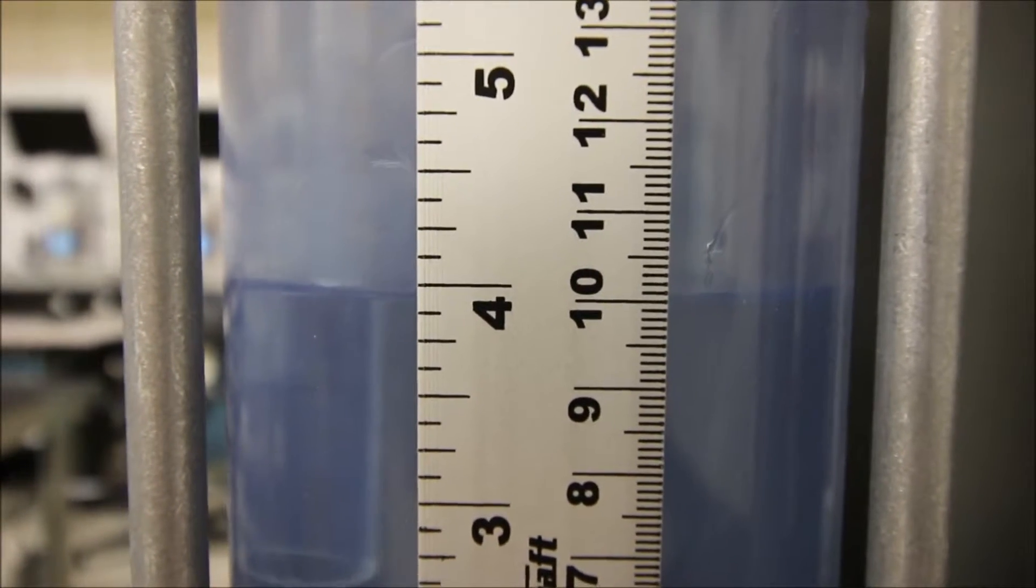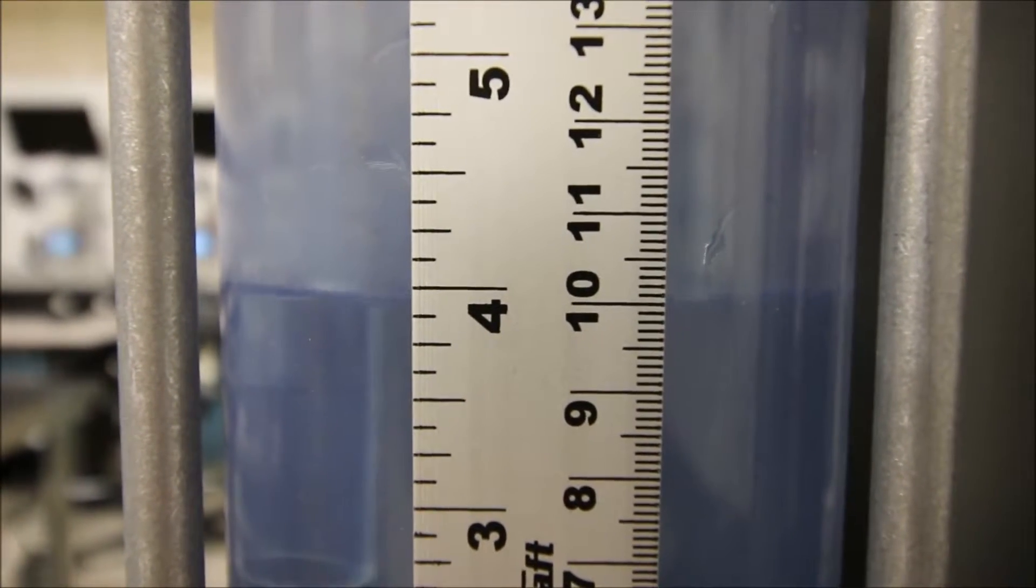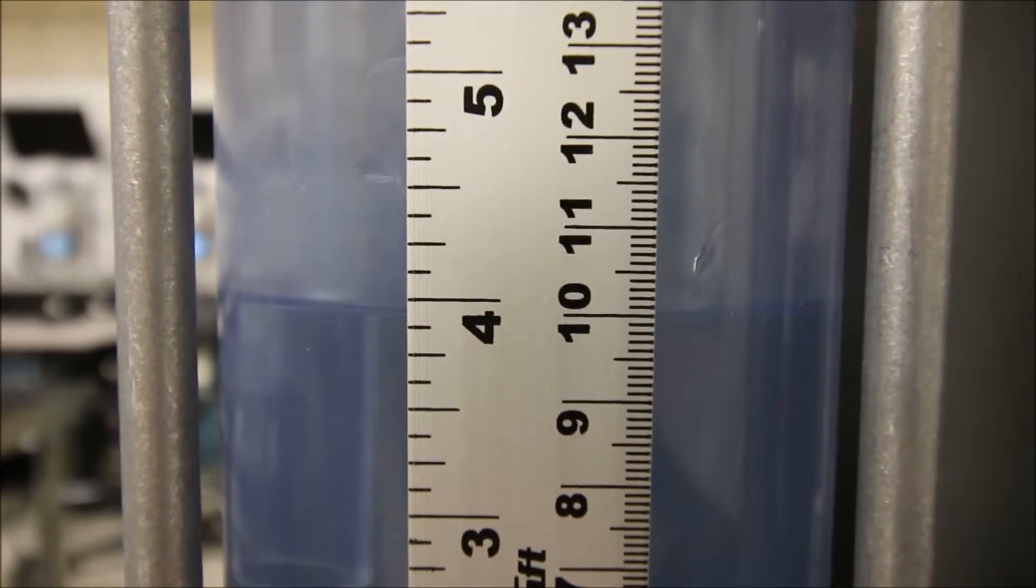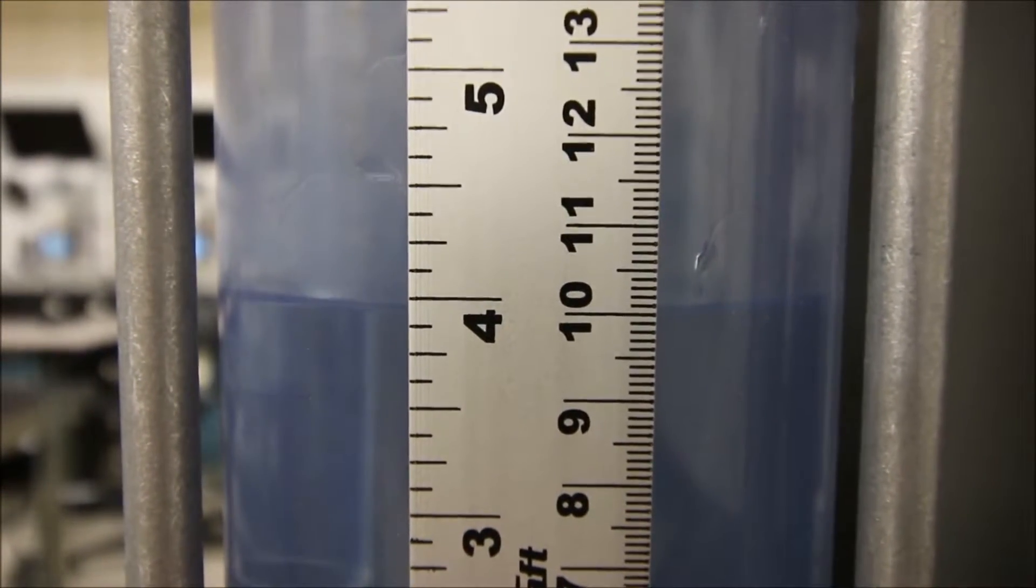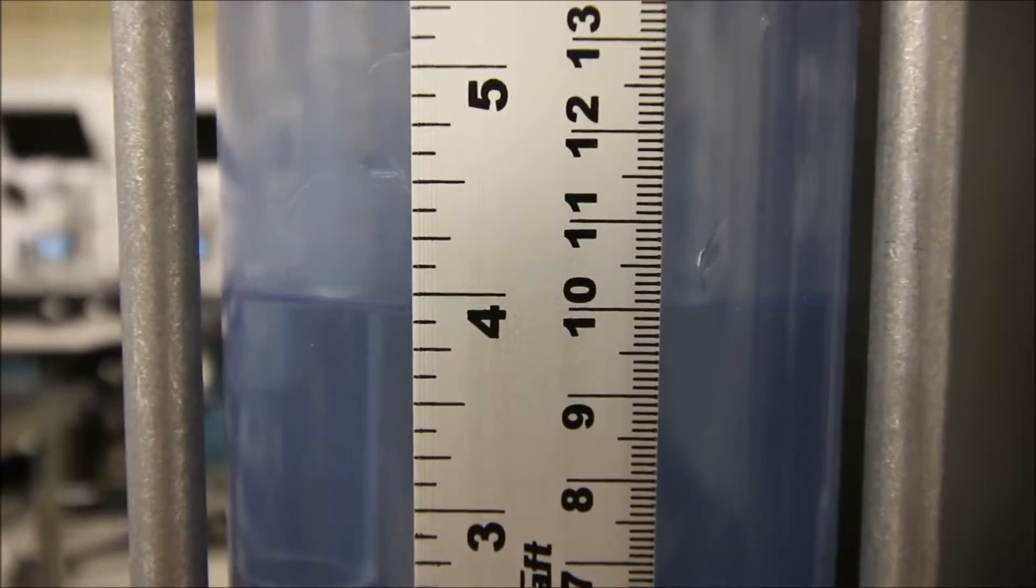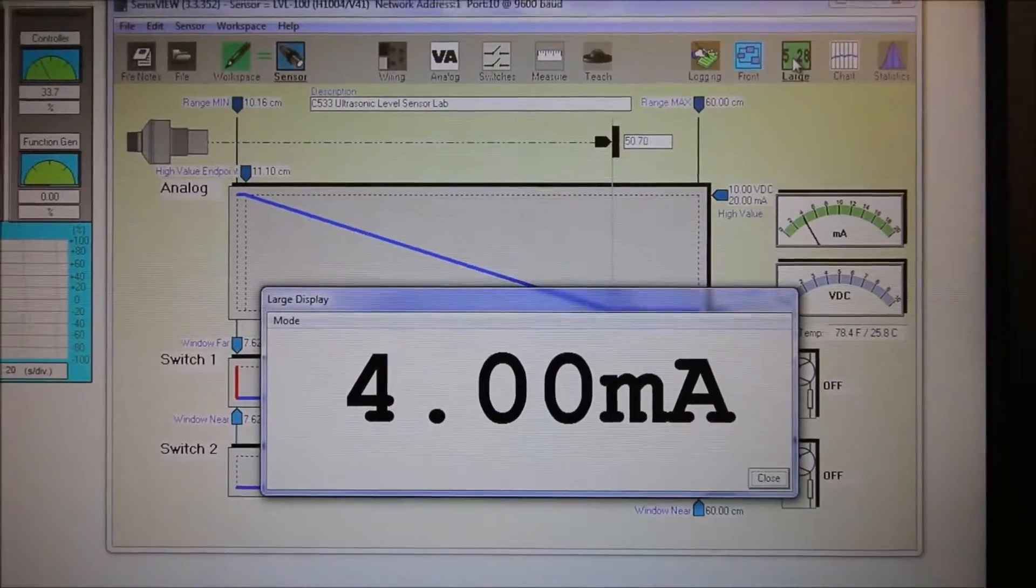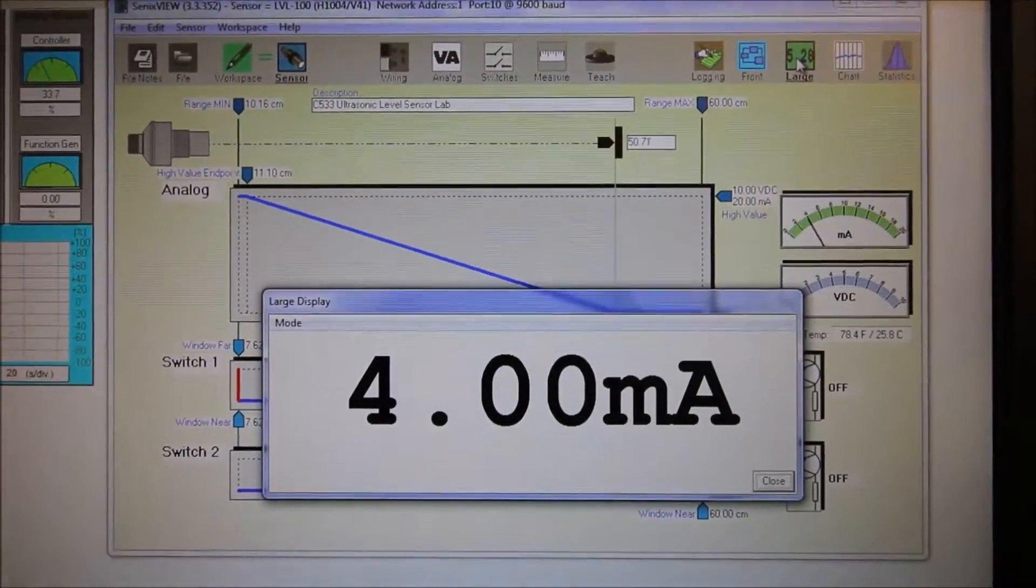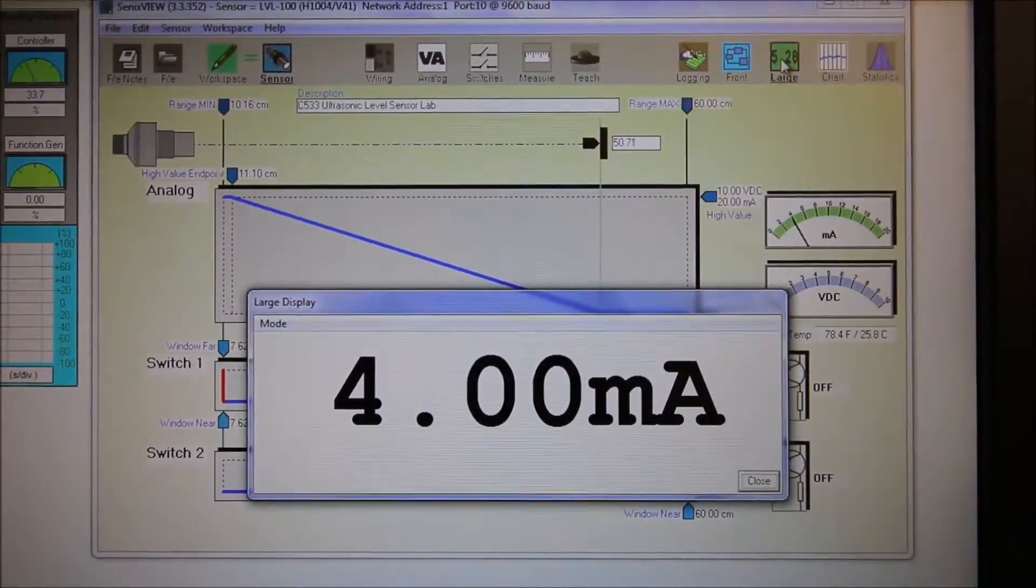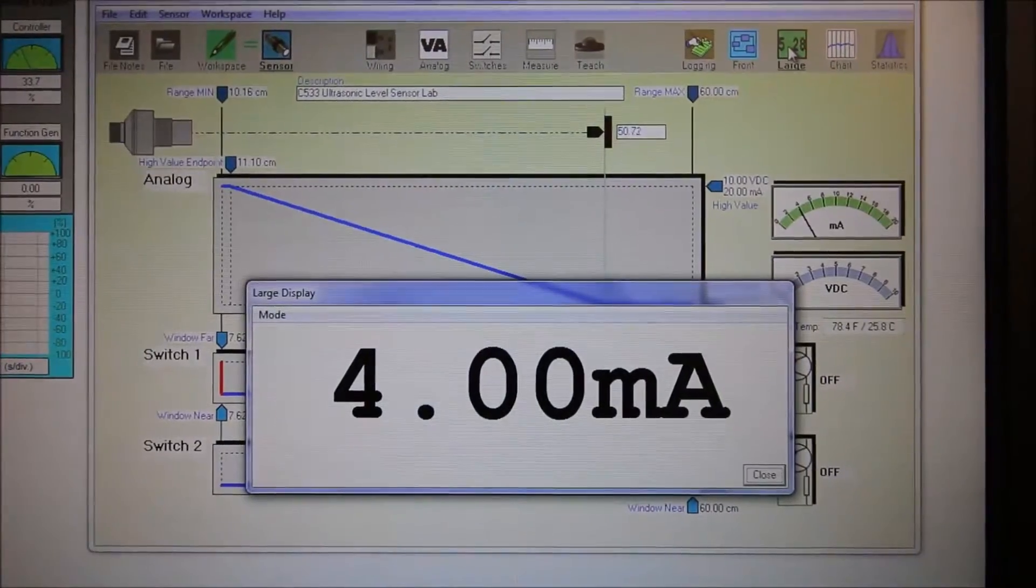Alright, so last measurement here. This is the lowest end of our range, we're at 10 centimeters in the tank, and we've set the 10 centimeters to give us our lowest current output of 4 milliamps. Nice, so this thing's deadly accurate. We're getting 4 milliamps now for our lowest end of the range.